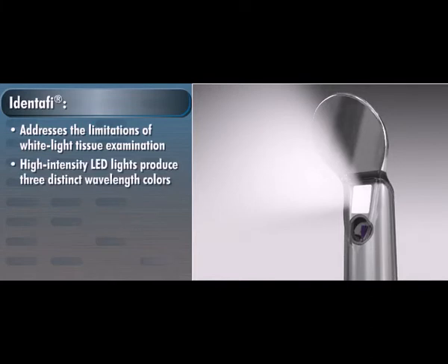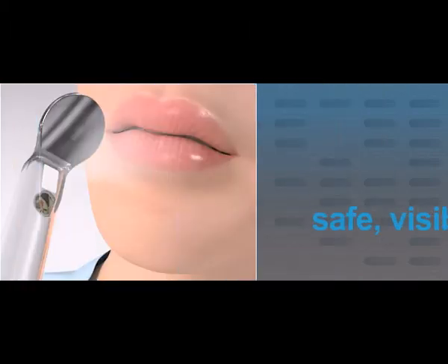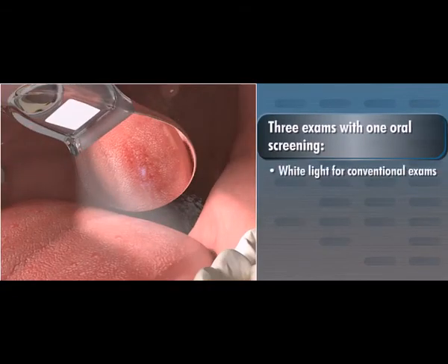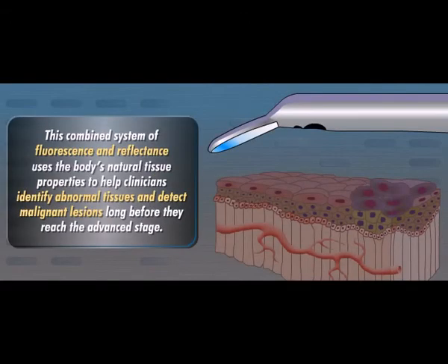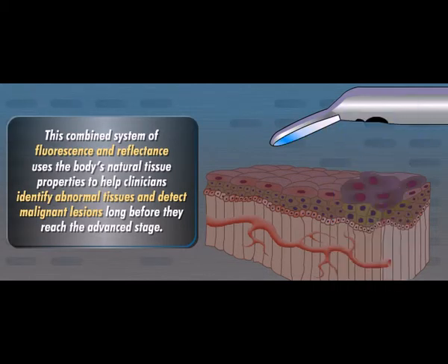Identafi is specifically designed to address the limitations of white light tissue examination. Its high-intensity LED lights produce three distinct wavelength colors — white, violet, and green amber — that excite oral tissue in unique ways, making it easier to identify lesion morphology and potentially malignant tissue. These safe, visible lights allow clinicians to conduct three exams with one oral cancer screening: white light for conventional exams, violet light for observing tissue fluorescence, and green amber for observing tissue reflectance and vasculature. This combined system uses the body's natural tissue properties to help clinicians detect malignant lesions long before they reach the advanced stage.